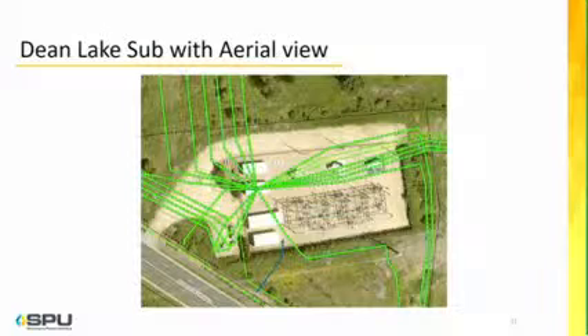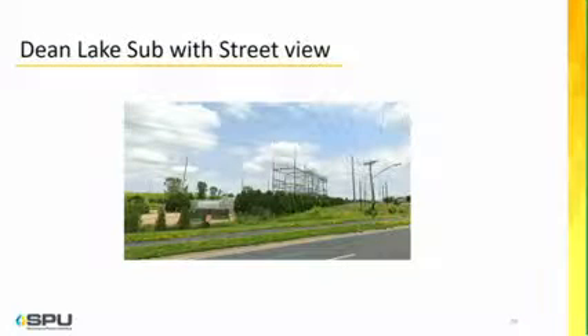What we did here was two things. We first selected to use a larger air gap. So our substation is actually 115 kV, but it's insulated to 161 kV, the next level up. So it's a bigger air gap between everything to prevent those flashovers. And then the other thing we did was all these insulators have a small current induced on them that repels the salt spray. So we didn't need the large netting. We were down in a hollow below the freeway because it's elevated. That wasn't really going to work, Xcel said. So we teamed with an engineer out of Canada to come up with the special insulators, and we also paid to upgrade the superstructure so it's really insulated for 161 kV.